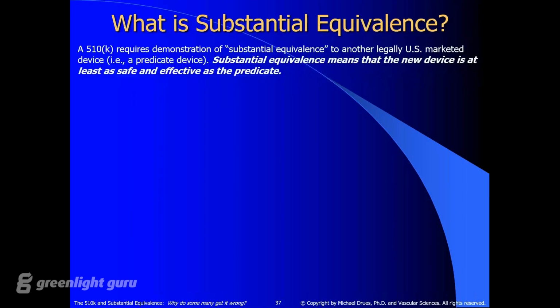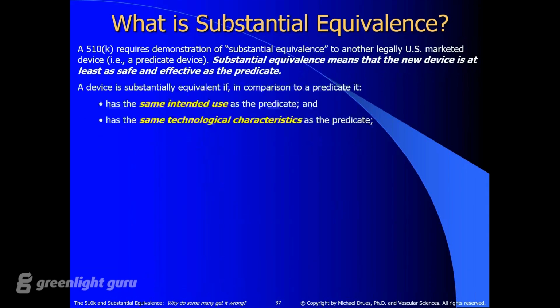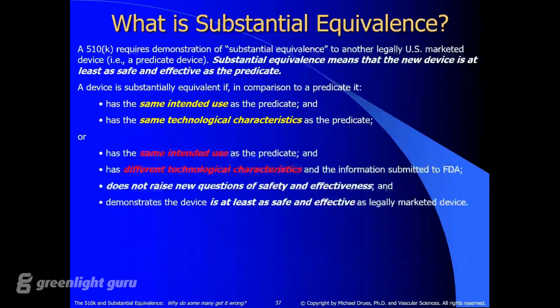So what the regulation says: substantial equivalence means that a new device is at least as safe and effective as a predicate. And substantial equivalence means that we have the same intended use and the same technological characteristics as the predicate. Okay, that makes sense. Or the same intended use and different technological characteristics. What the heck does that mean? I have no idea. And again, I hope everybody appreciates my not-so-subtle use of humor here, because this is exactly what the regulation has said since 1976: the same intended use and the same technological characteristics, or the same intended use and different technological characteristics. And if it does have different technological characteristics, these differences in technology cannot raise additional questions of safety and efficacy, of risk, and so on and so on.